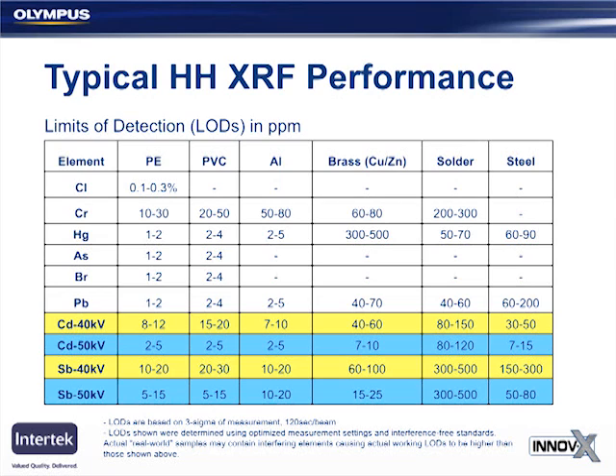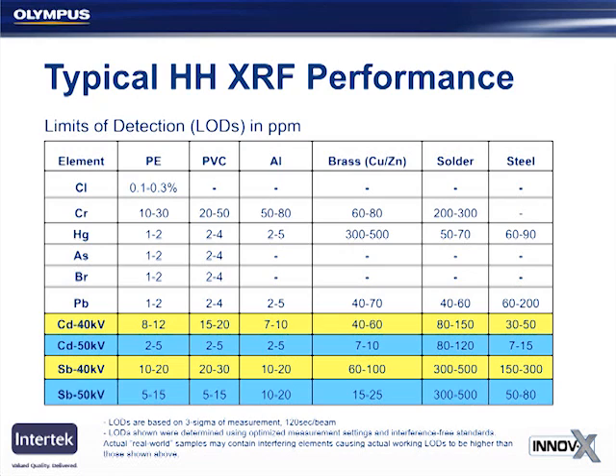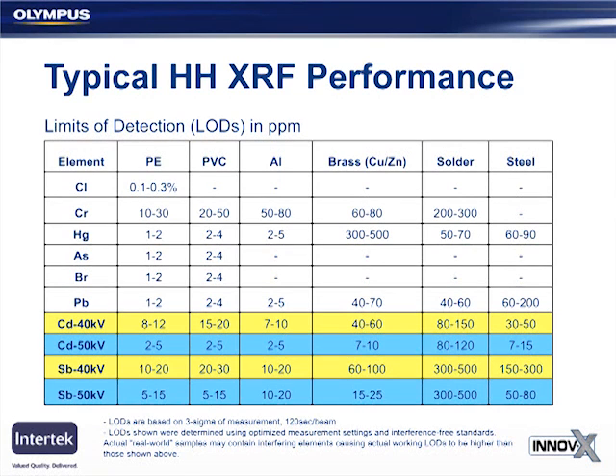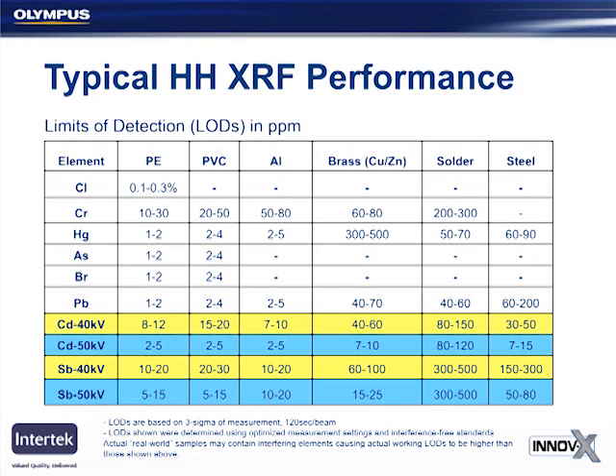I also mentioned earlier the X-ray tube voltage that you're using, 40 kilovolts versus 50 kilovolts. It's mainly helpful for certain heavier elements that have higher energy emission lines, so the tube voltage will mainly have an impact on those. 40 versus 50 kV won't have as much of an impact on the other elements. Again, these are typical LODs based on ideal homogeneous samples. They do vary based on application, but this is just to give you a broad overview of what sort of performance XRF can reach.